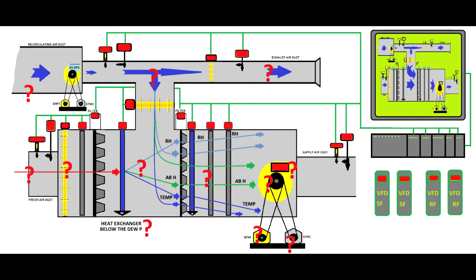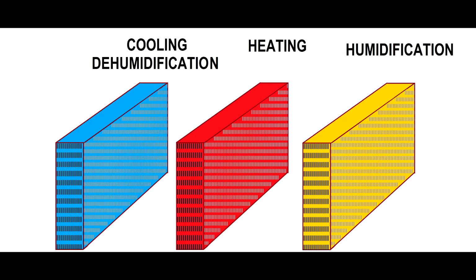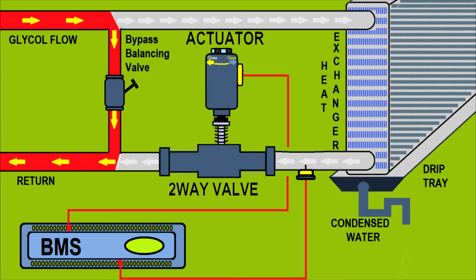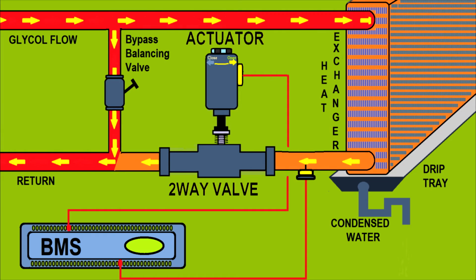Dear friends, we go through a lot of boring things about the AHUs. We talked about these heat exchangers, why they're so important, the valves that allow the cooling or heating agent to pass by so the heat exchanger will be either cool or heated, the humidifiers that need to compensate for the lack of humidity when we're running very cold heat exchangers.